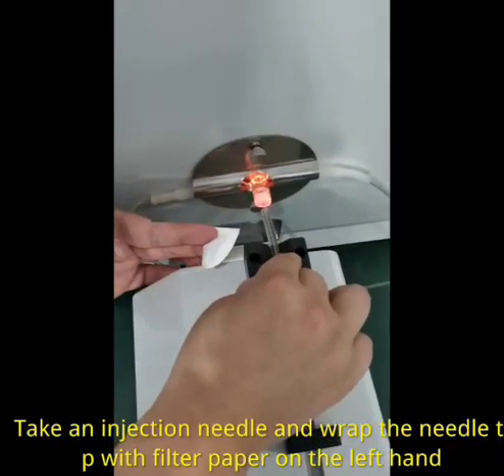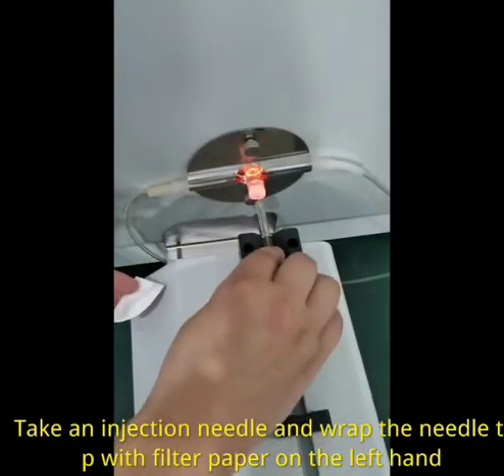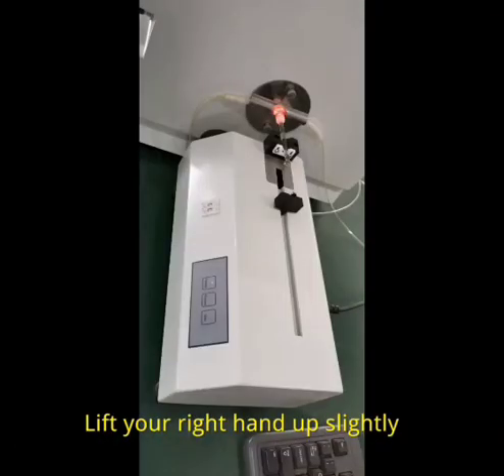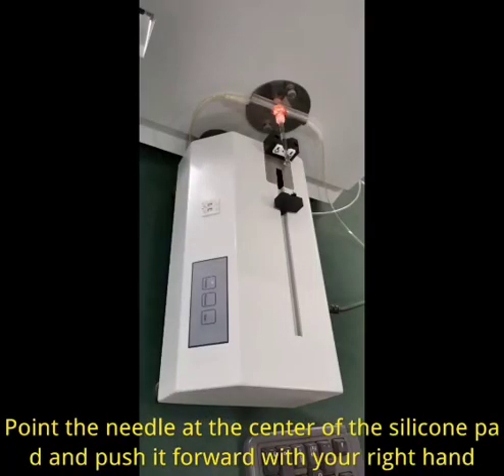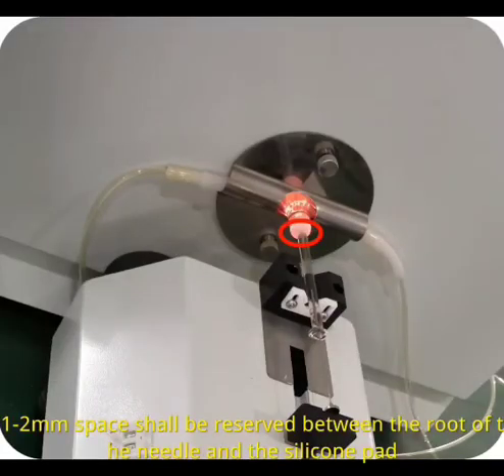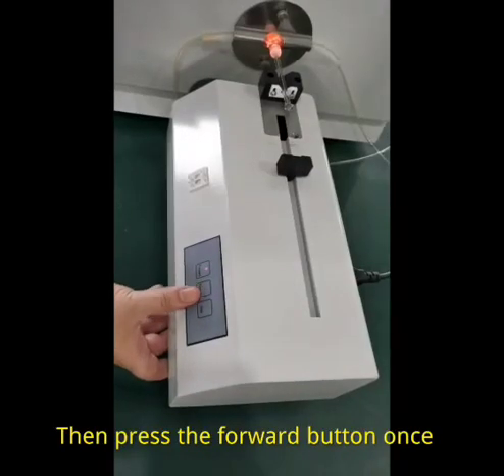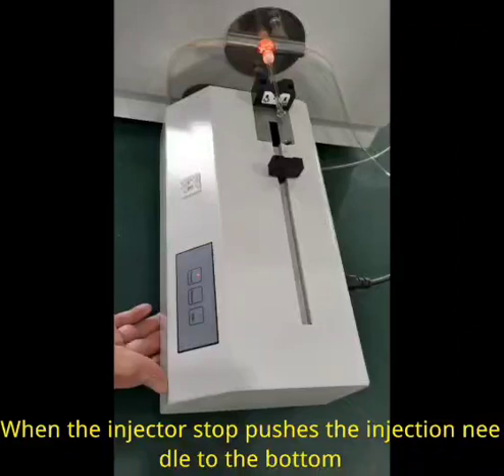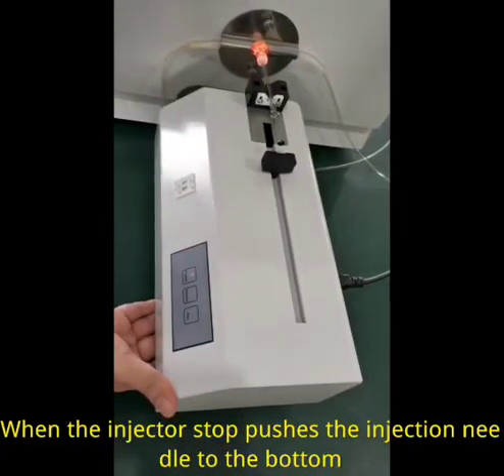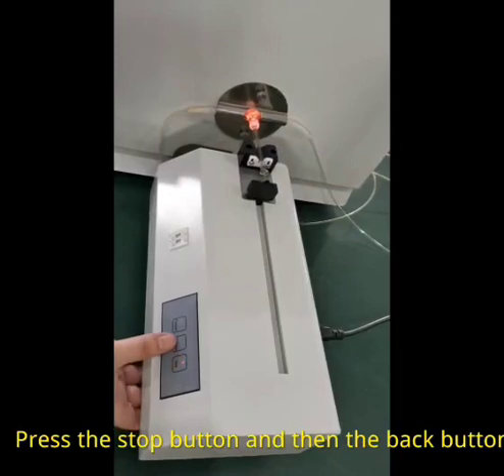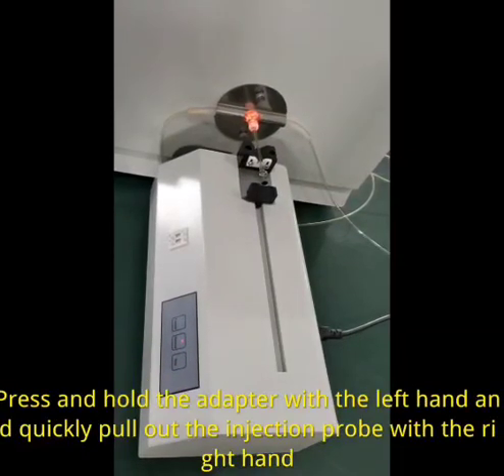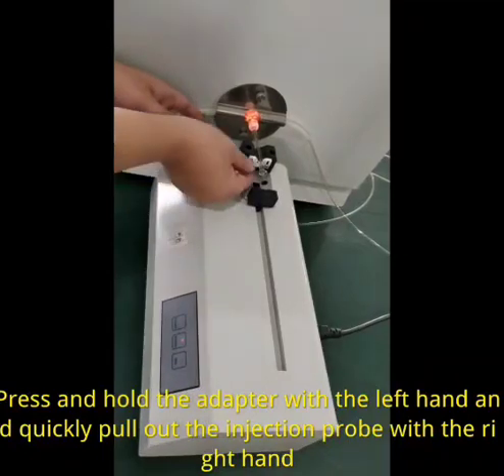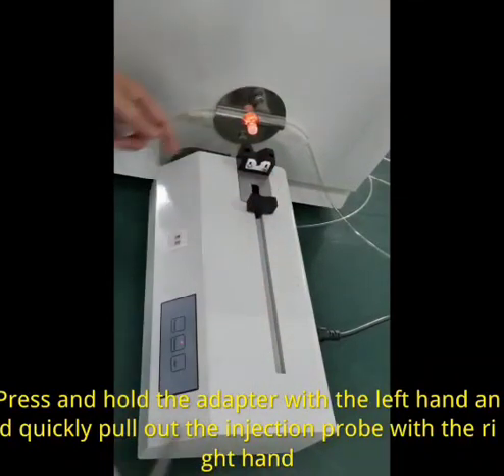Take an injection needle and wrap the needle tip with filter paper on the left hand. Lift your right hand up slightly. Point the needle at the center of the silicone pad and push it forward with your right hand. 1 to 2 mm space shall be reserved between the root of the needle and the silicone pad. Then press the forward button once. When the injector stop pushes the injection needle to the bottom, press the stop button and then the back button. Press and hold the adapter with the left hand and quickly pull out the injection probe with the right hand.